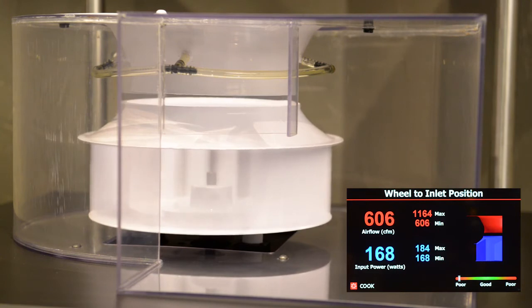Continuing down, the whistle goes away and the gap between the wheel and inlet is clearly visible, allowing air to recirculate from the discharge of the wheel to the inlet with a significant reduction in the fan output. Still, the power consumption is relatively constant.